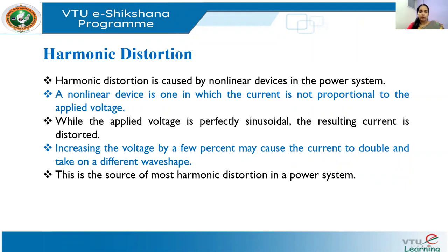Such loads are called non-linear loads. Examples include any load containing a power electronic converter, such as adjustable speed drives, motor drives, fluorescent lamps, induction furnaces, and arc furnaces. In non-linear loads, the current is not proportional to the applied voltage, even if that voltage is a perfectly sinusoidal waveform as produced in our power plants.